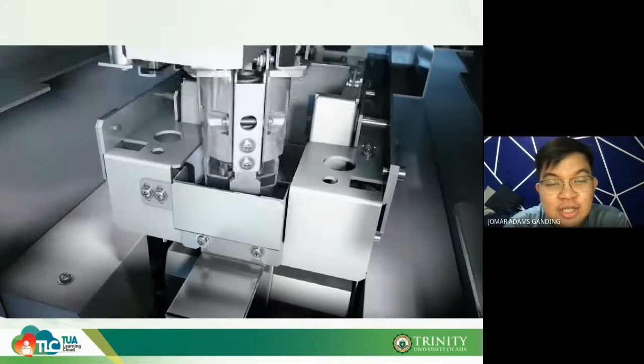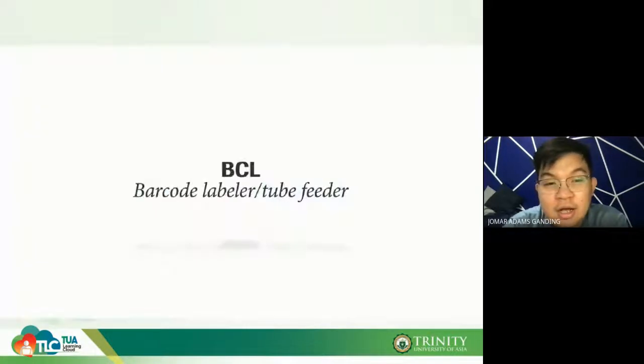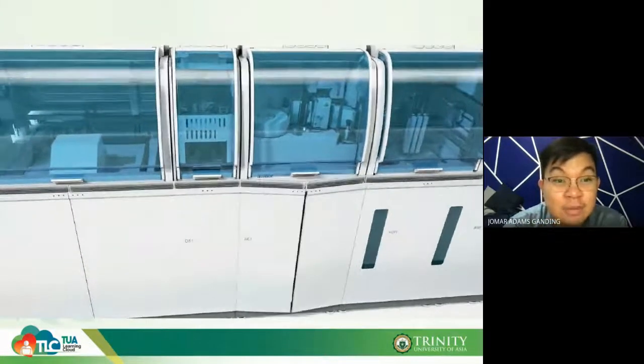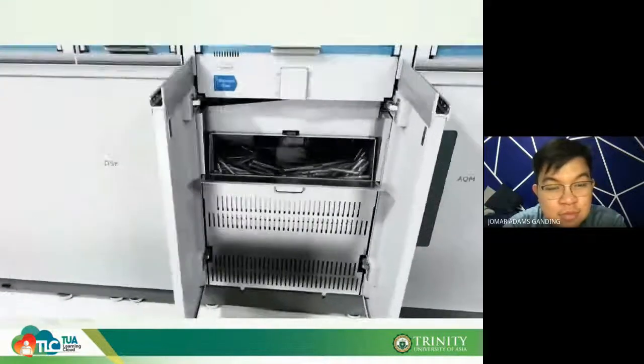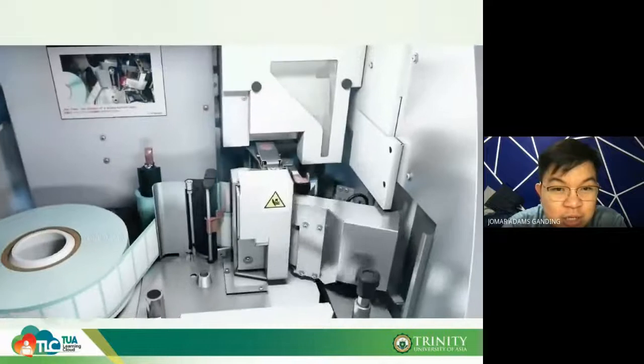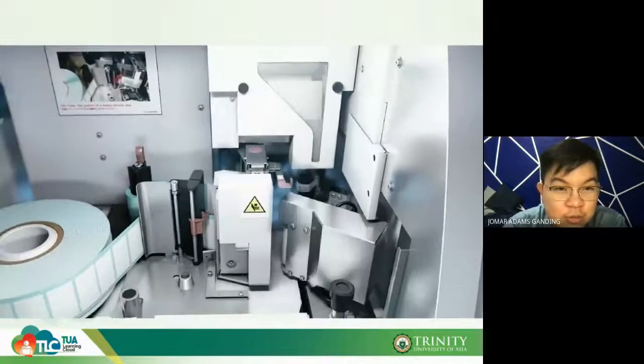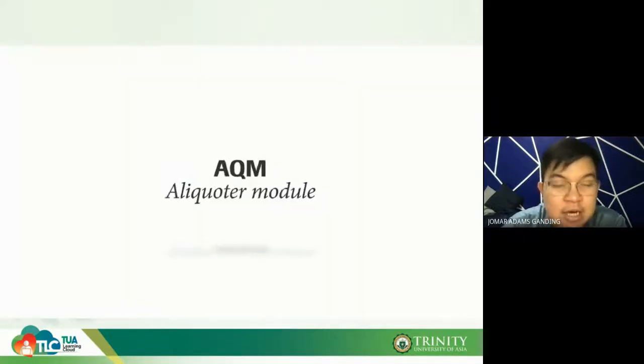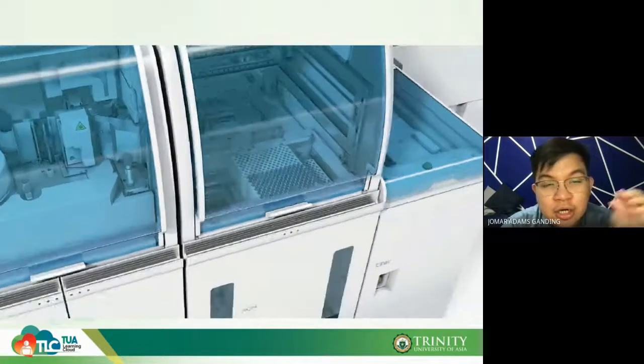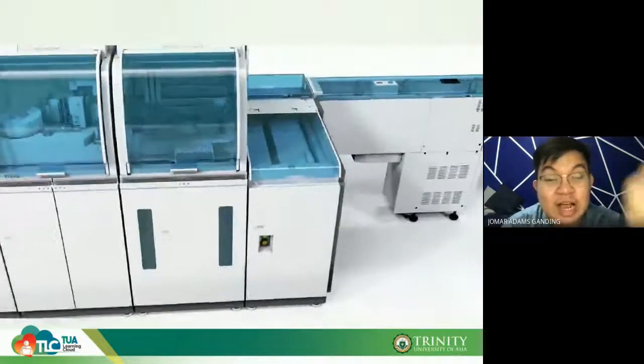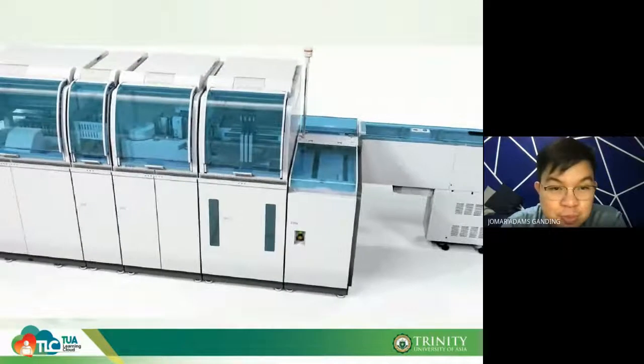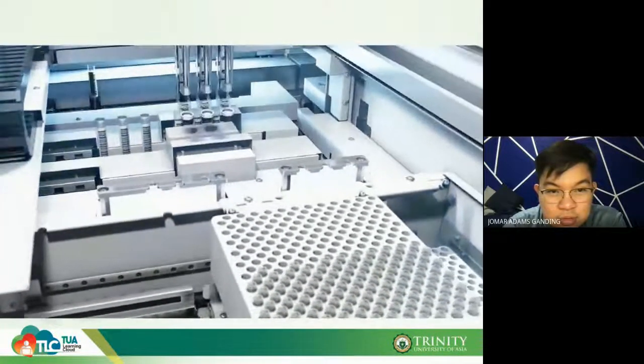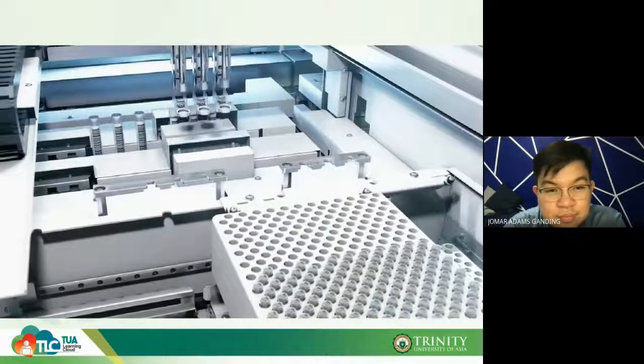While the stoppers are being removed, the tubes are not lost because of the tracking system. The machine then performs aliquoting — labeling the aliquot tubes and transferring the sample from the mother tube to the aliquot tubes automatically.